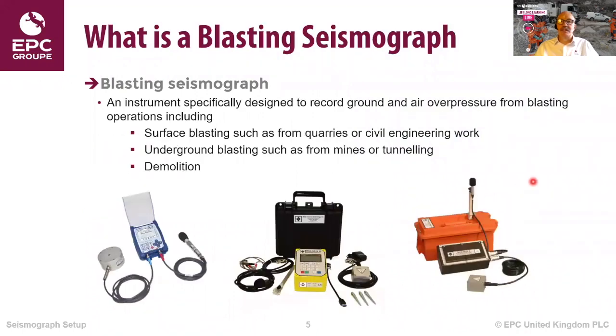So first of all, what is a blasting seismograph? Well, it's an instrument specifically designed for the industries using explosives, because we wish to record ground vibration, and we wish to record vibration through the air, generally known as air overpressure. And that's from any blasting operation. That can include surface blasting, such as from quarries, or civil engineering works, say road cuttings, things like that. But also underground blasting, such as from mines or civil engineering tunneling works, or even demolition of buildings. So anything using explosives will generally have some form of requirement to record the environmental impact, both ground vibration and air overpressure.